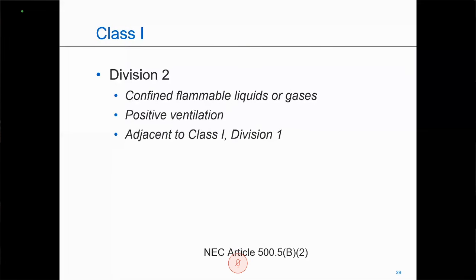Now, Class 1, Division 2 is where a fault condition is needed for the gases and vapors to become present. Or you might have an area that would normally have been Class 1, Division 1, but through positive ventilation and changes of air, the area may be able to be derated to a Class 1, Division 2 area. And whenever I have a Class 1, Division 1 area, you're typically going to have an adjacent area that is Class 1, Division 2. So if I get back to the paint booth example, that's going to be Class 1, Division 1. And with that application, a 3-foot envelope in every direction outside the door of the paint booth is going to be Class 1, Division 2.